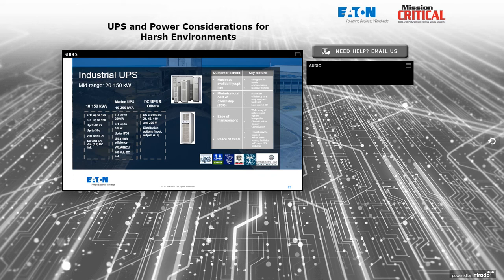So if you are considering a 3-phase in, single-phase out, it is possible to procure those from a variety of industrial UPS vendors. Far more common, though, to see 3-phase in and 3-phase out, especially in this 10 to 200 kVA range. Marine UPSs go up to as large as 200 kilowatts. Some of those are 3-phase in and single-phase out, at least up to 30 kilowatts. They're more likely to require a special IP54 enclosure. It's important to have ultra-high efficiency in any UPS. They may have a 400-volt DC link to match up with some of the DC systems that are operating on commercial ships for that type of transportation nowadays.